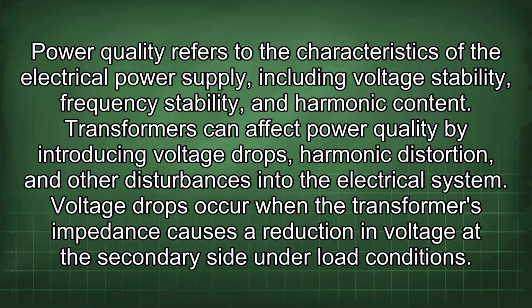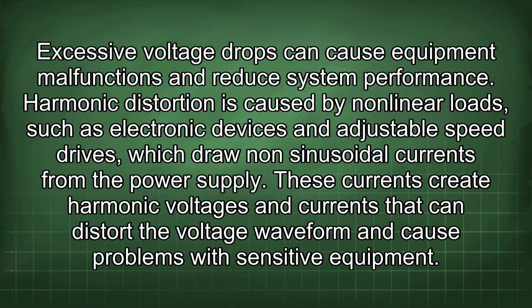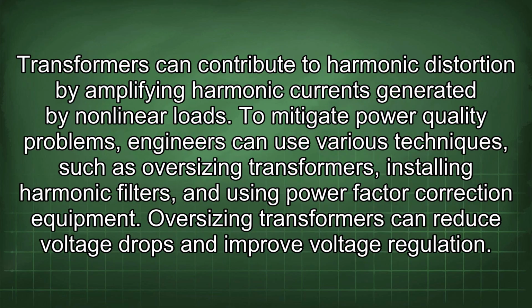Transformers can affect power quality by introducing voltage drops, harmonic distortion, and other disturbances into the electrical system. Voltage drops occur when the transformer's impedance causes a reduction in voltage at the secondary side under load conditions. Excessive voltage drops can cause equipment malfunctions and reduce system performance. Harmonic distortion is caused by nonlinear loads such as electronic devices and adjustable speed drives, which draw non-sinusoidal currents from the power supply. These currents create harmonic voltages and currents that can distort the voltage waveform and cause problems with sensitive equipment. Transformers can contribute to harmonic distortion by amplifying harmonic currents generated by nonlinear loads.